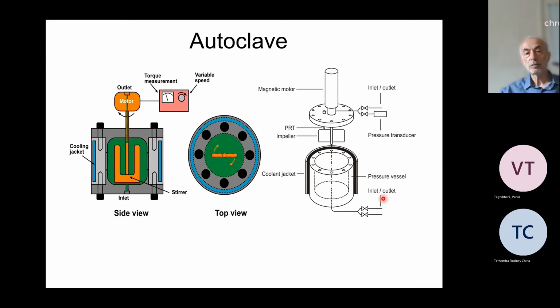This is the internal shape of this cell. You can see it has a mixer, you can increase pressure, there's an inlet and outlet, and this is the magnetic motor. We measure torque, and this is the impeller. This is a temperature probe, a PRT, and we have a cooling jacket around it for pressure testing. Basically we do tests here — this is the cooling jacket, this is torque measurement, and this is mixing. Different shapes and sizes of mixer can be put in the cell.